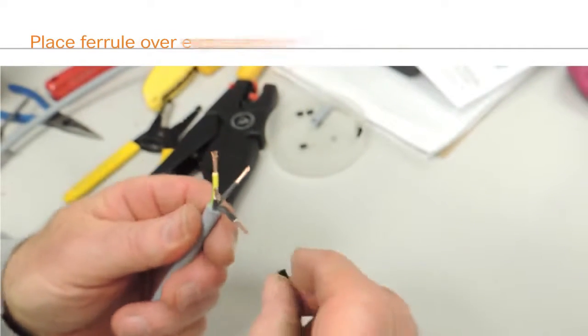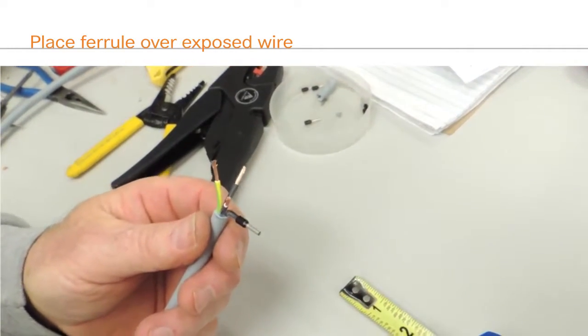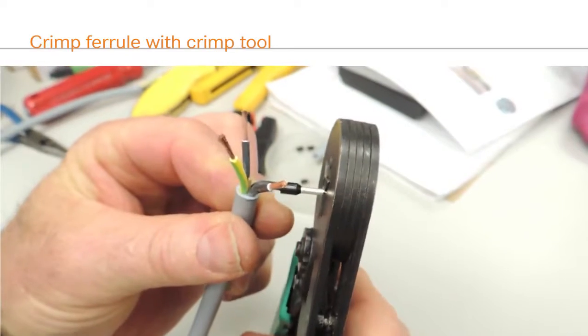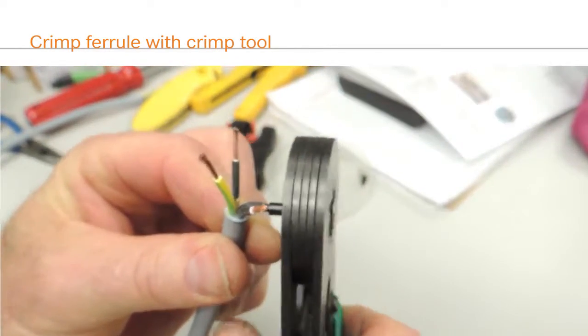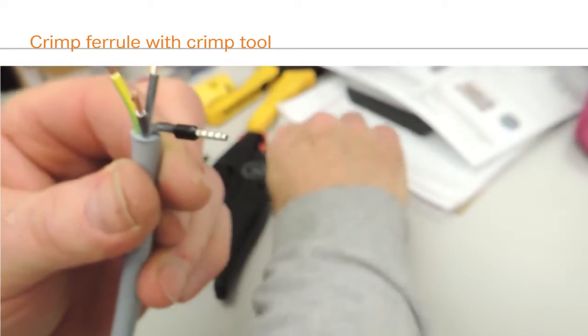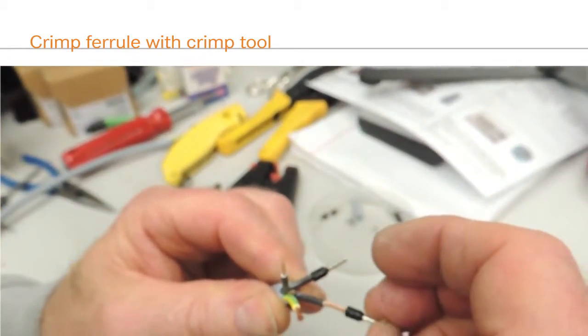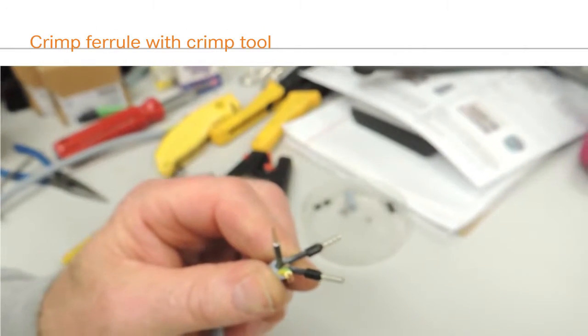To attach the ferrules, simply place the wire into the ferrule. You should be able to see the wire at the end of the ferrule. If there is not enough exposed wire in the ferrule to do this, strip the insulation back further. Now, crimp the ferrule to the wire using the crimping tool. Repeat the process with the remaining conductors.